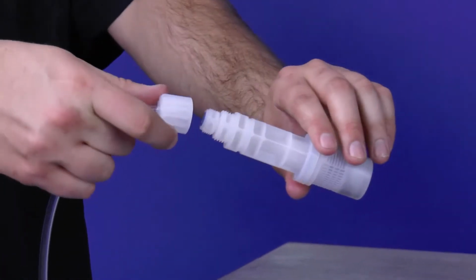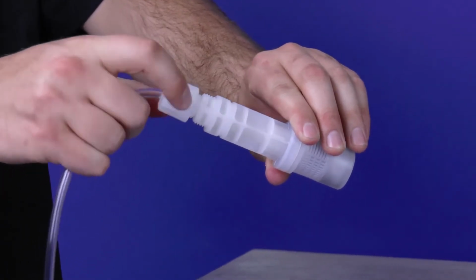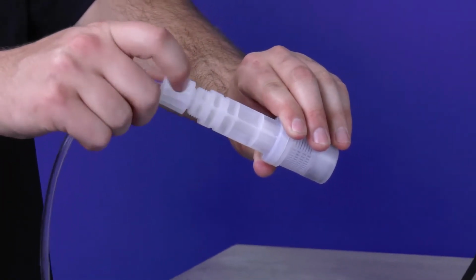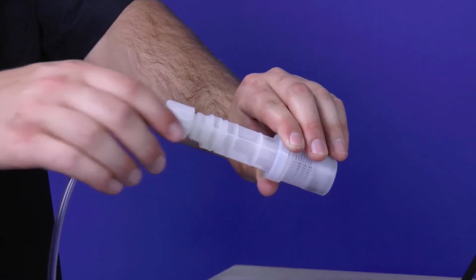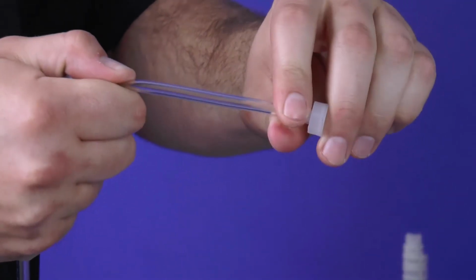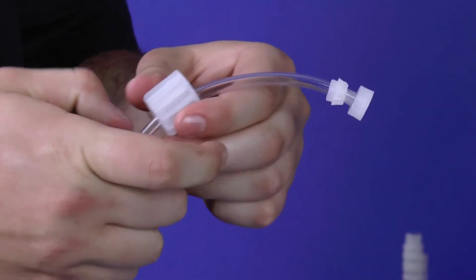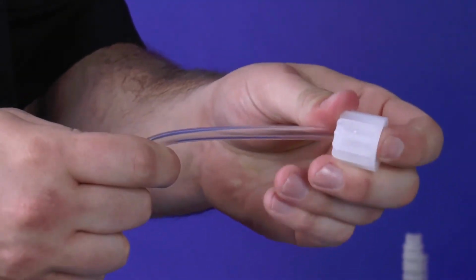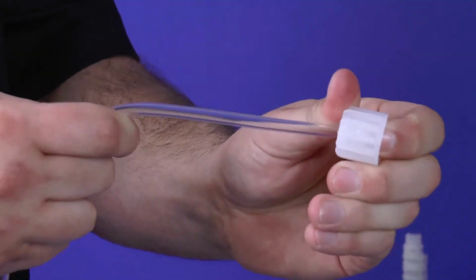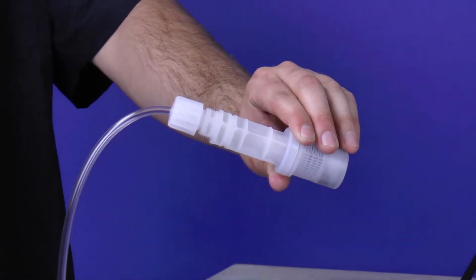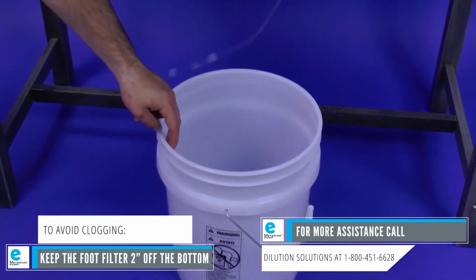Grab the foot filter and reattach the tube and tube connections onto the foot filter by hand tightening the tube nut. Do not cross-thread nor over-tighten. If the tube nut is not securing, recheck the ferrule connection. Pull the tube nut toward the nozzle once more to compress the collar and nozzle together. Retighten the tube nut until secure. Place the foot filter into the bucket or stock tank. This ensures the foot filter draws chemistry once you begin operation.